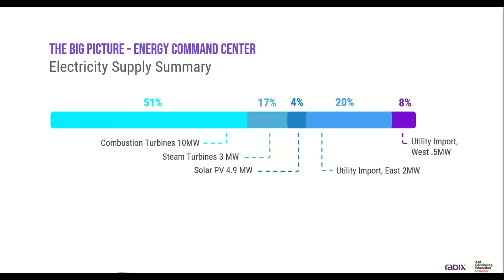Over the years we can generate about 80% of the campus electrical needs. Now that we've tied the east and west side together, we've actually got ourselves a little closer to 90%. Here you can see that 51%. This is from the 2019 data. So we have 50% came from the gas turbine, another 17% from the steam turbines, 4% from solar, and then the import from the east and west side. This comes up slightly under our 80%, but this was a project year. We were doing quite a few things, but normally we would run around 80%, and we recently improved to about 90%.